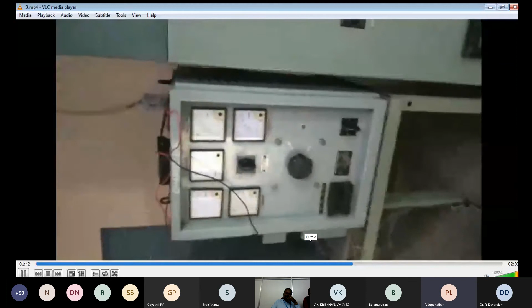This is a battery bank room, and these batteries are required. These are electrolyte lead acid batteries. These batteries are very much essential, the heart of the substation for controlling all the relay panels. So every shift, operators have to check the DC voltage and the specific gravity of the battery cell and everything. In each shift they have to measure it. There is a pilot cell available, and the pilot cell reading they have to take.